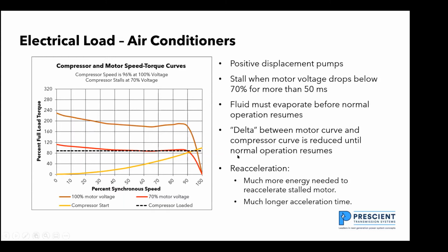Air conditioners have the same characteristics, except I have to add another characteristic in here. And this is the positive displacement hysteresis curve for the motor, for the compressor. Once I get the air conditioner running, I have to maintain 80% voltage in order to have the air conditioner not stall. So what happens is when I get to 70% voltage for more than 50 milliseconds, air conditioners start stalling, and they don't resume normal operation until the fluid evaporates.